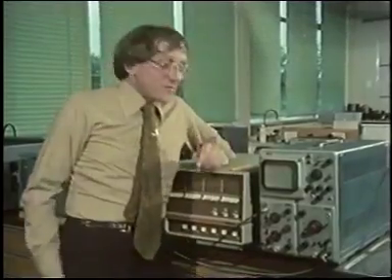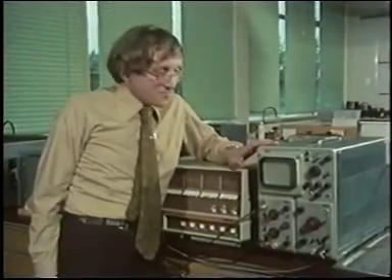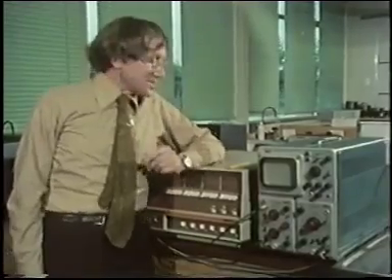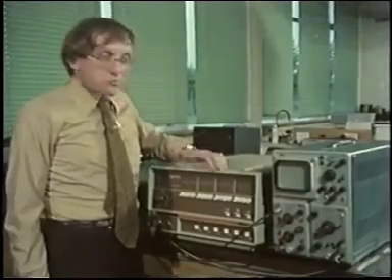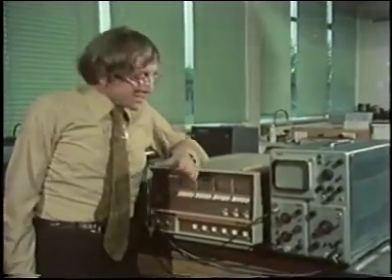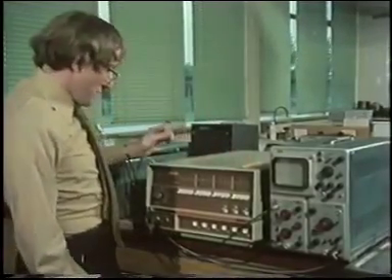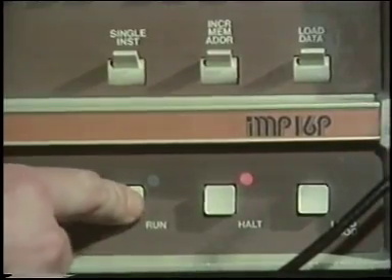But we must be rather careful. What we're seeing on the oscilloscope here is not the spectrum of the radiation that's striking the detector. In fact, it's merely an interferogram. Well, we know that to get from an interferogram to a spectrum, we've got to take a Fourier transform. And that's where this miniature computer comes in. All the while that I've been talking, it's been storing information from the Michelson. And we'll now ask it to take the Fourier transform of the interferogram for us.